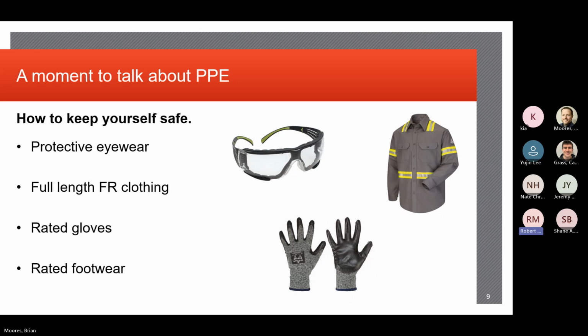Yeah. We have steel toes, eyeglasses, and hard hats where I work. Yep. Yeah, and again, we're out in the field with these relays, all in substations or cubicles, switchgear, etc. So you're prone to voltage, high voltage, arc flash. So at a minimum, your Z87 rated PPE safety glasses, appropriately arc flash and FR rated clothing, long sleeve, or natural fibers, but generally FR is required, mandatory.